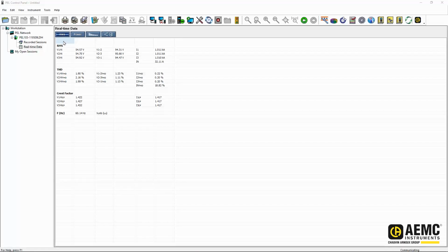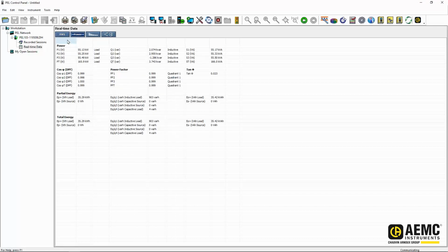RMS data is also available for my voltage, current, and frequency, plus all my calculated power quantities can be displayed in real time. I can quickly check to ensure my phases are equally balanced and I have acceptable power factor on my system. That's it. My PEL is recording, my values look acceptable, and we're ready for the next project.